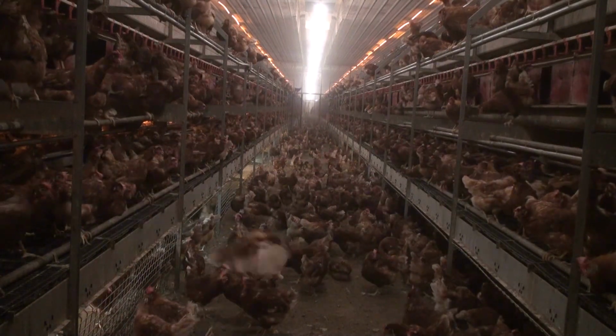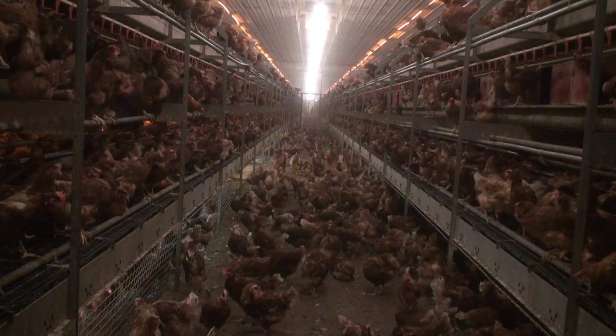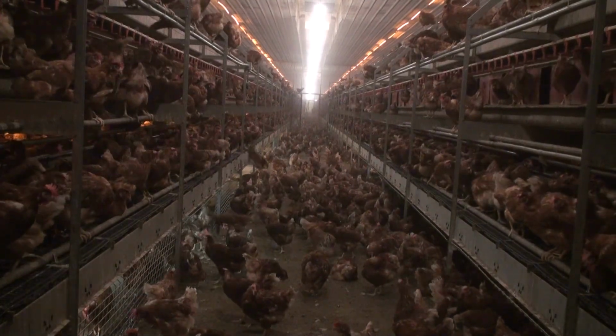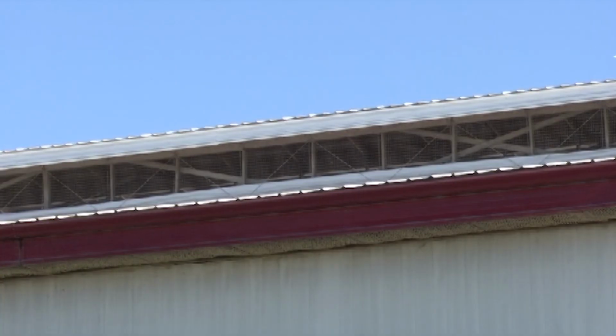In the winter, this is an advantage for maintaining the house temperature, but in the summer heat, the added 10.5 mil BTU can become a problem. Most poultry houses utilize a negative static pressure ventilation system with perimeter intake vents. This means the ventilation fans are actually pulling more air out of the house than the intake vents will allow in. In the summer, this results in a tremendous volume of air.